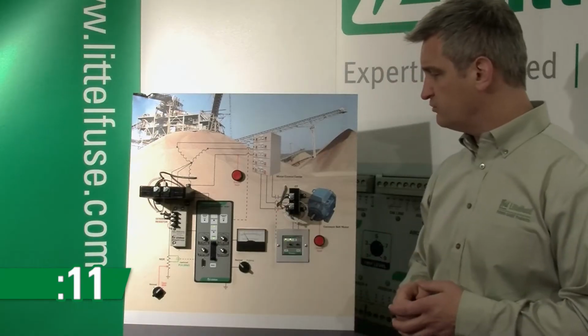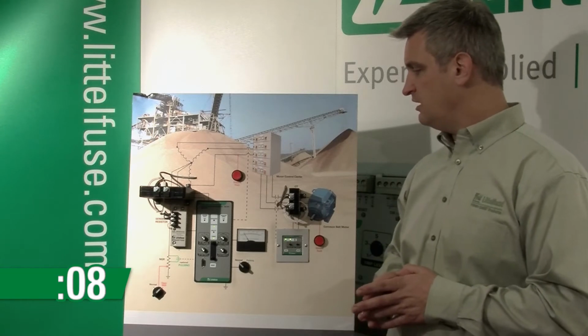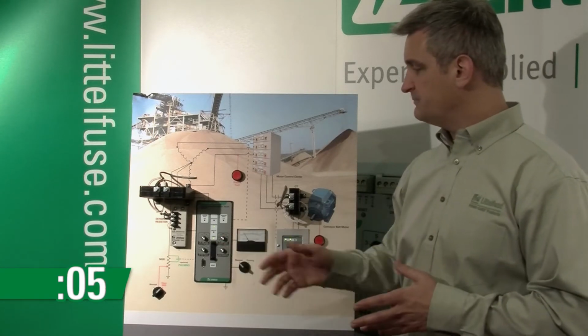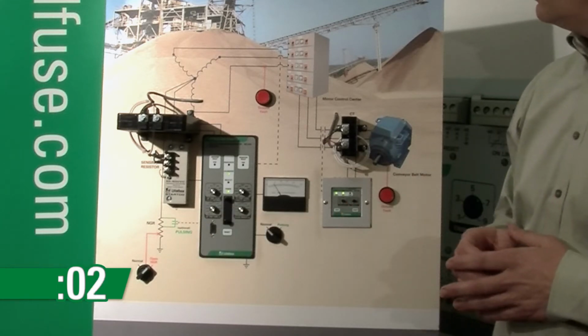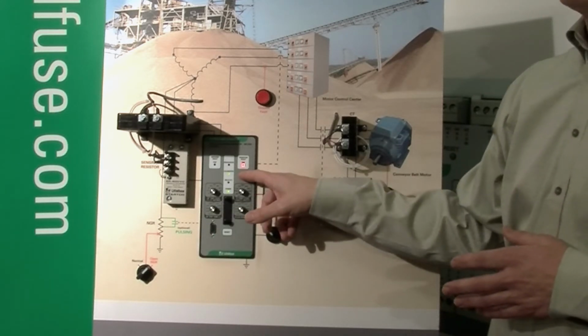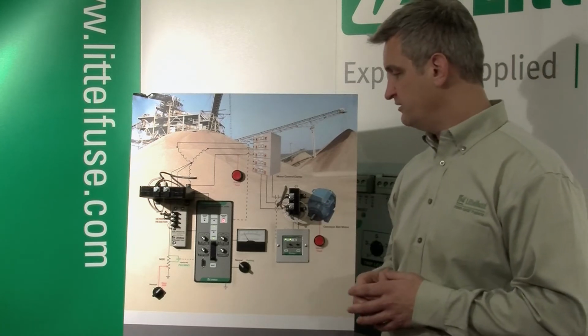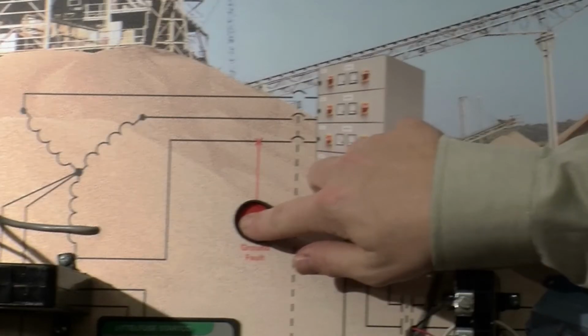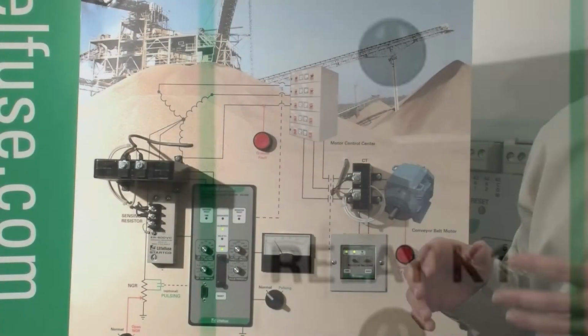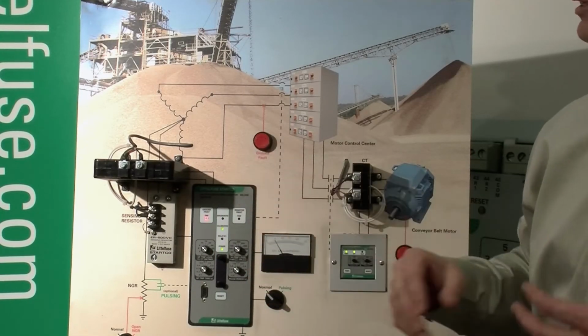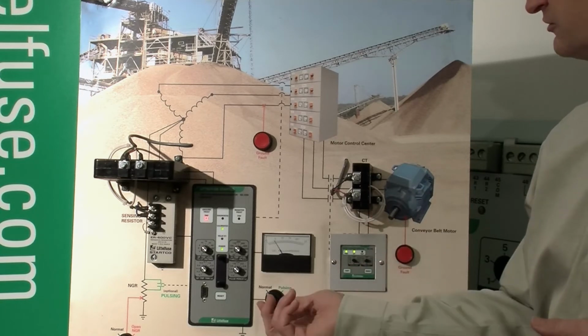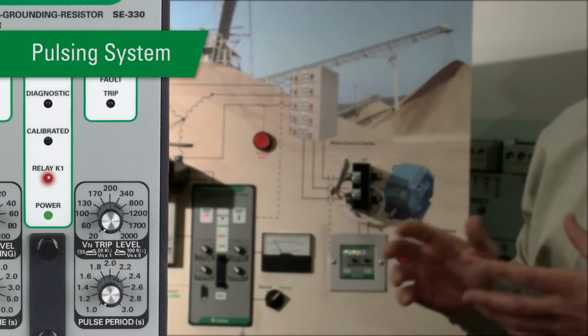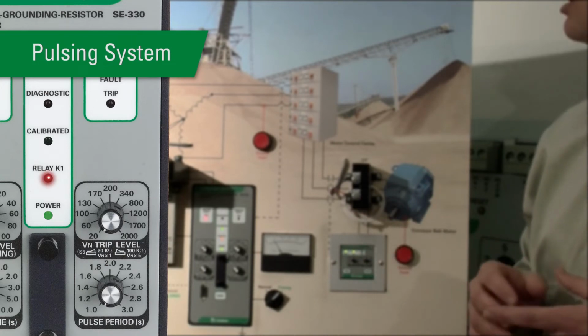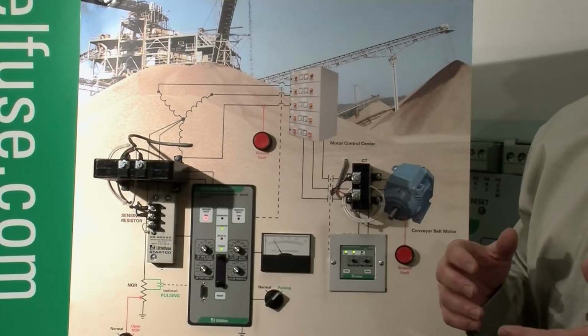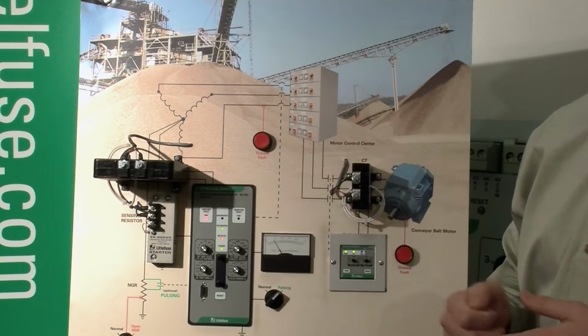There's a preset time delay of 12 seconds, so there are no transients, for safety reasons. So after the time delay, if for some reason the circuit does become open circuit, our SE330 here will detect it and send a signal out to the plant personnel. The other part of the SE330 is the ground fault detection I mentioned earlier. I'll just demonstrate that here. You can quickly see that if there's a ground fault, it detects it. Okay, so they know there's a ground fault on the system. The alarm comes out and says, now I need to go find the ground fault. They can use what's called a pulsing system. That alternates the current from a low value to a high value, cycling about once per second. The electrician then grabs his clamp-on ammeter and goes out and tracks down and finds the ground fault.